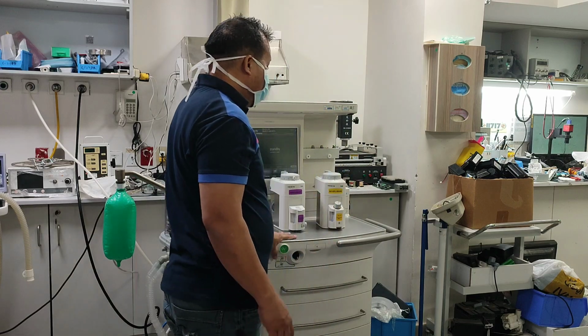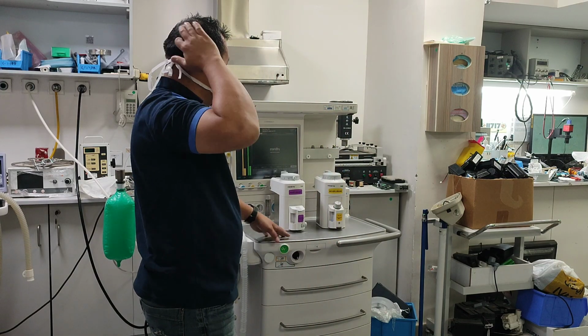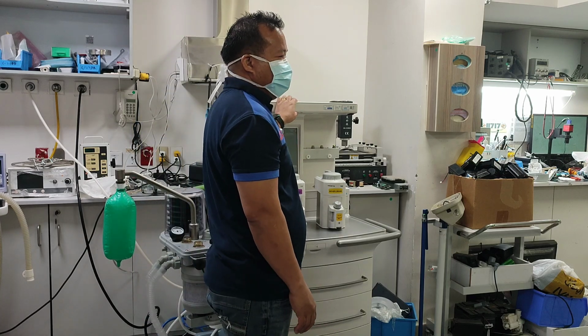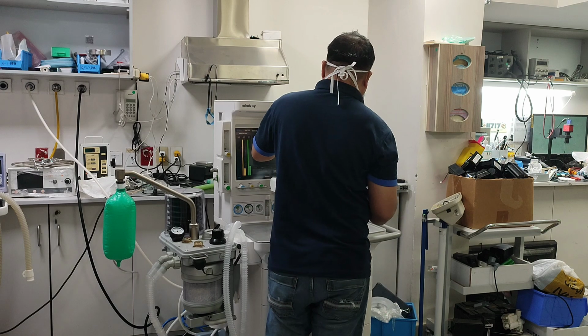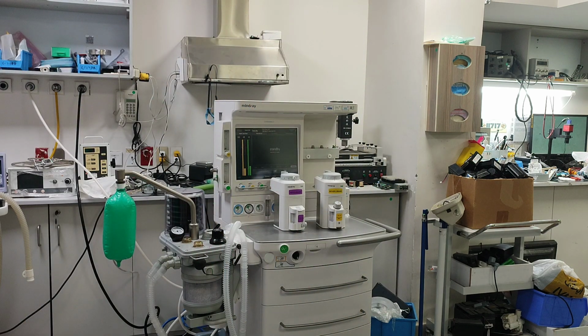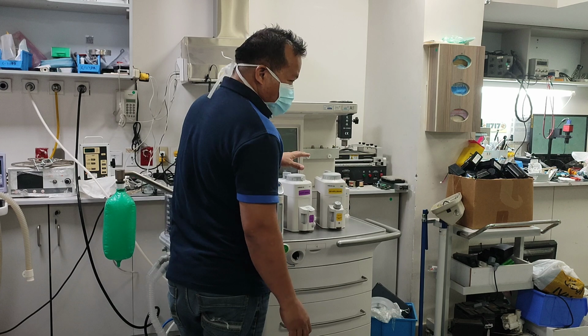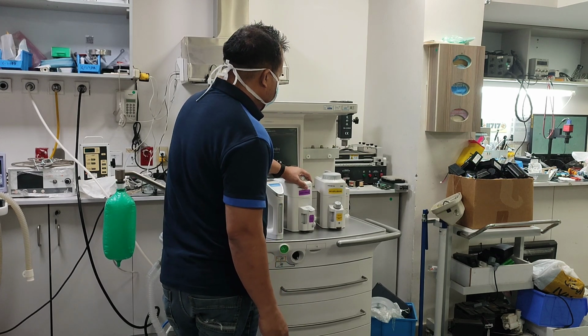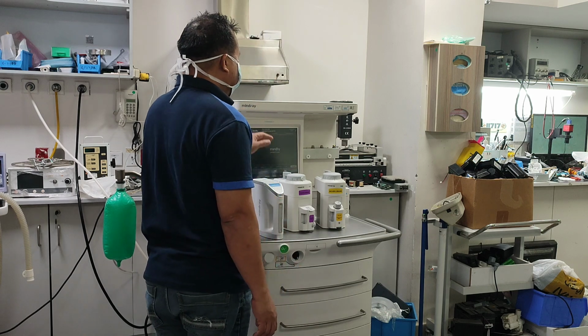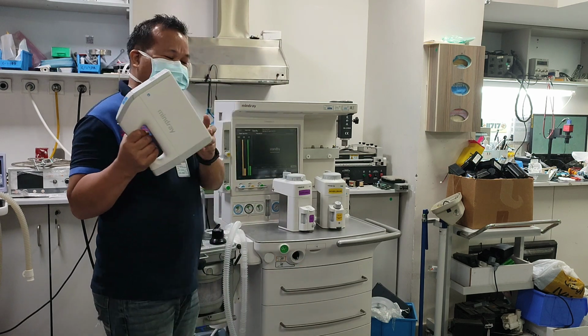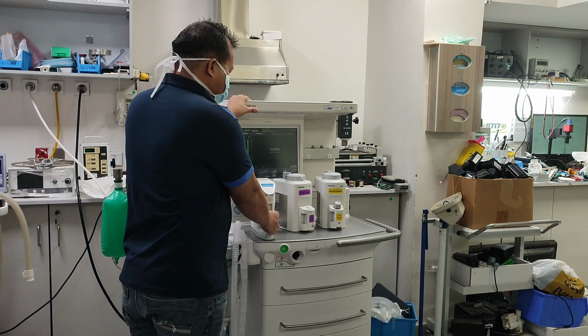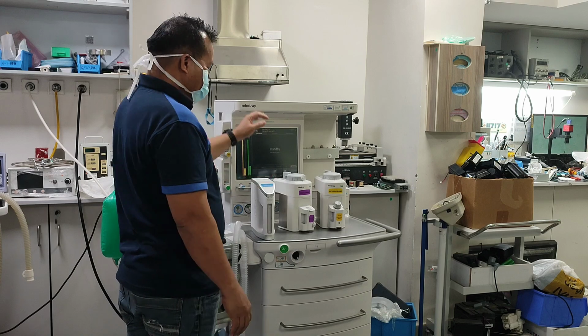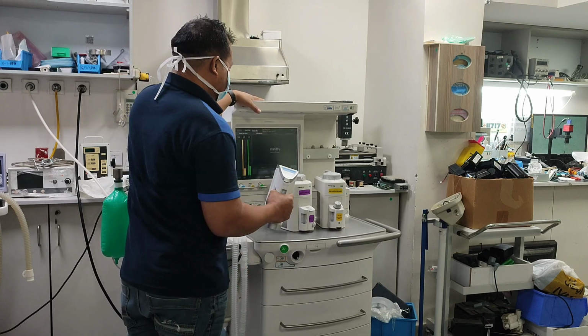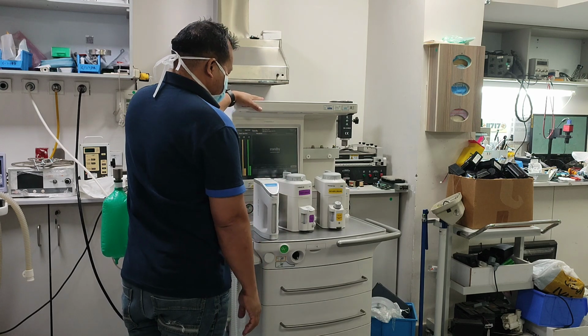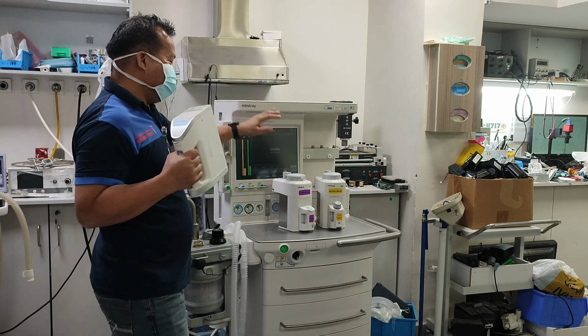But now in the new model, we have the new model now, this Mindray E9. No need to change all this because this one is electronic. Just push. I have one electronic vaporizer here. The new machine is different. This is for our old machine. For the new E9 anesthesia machine, this is the vaporizer that you see. It is electronic already. Once you put it in the machine, it will automatically lock the vaporizer. So no need to do anything. This is the new technology now. This is the old technology.